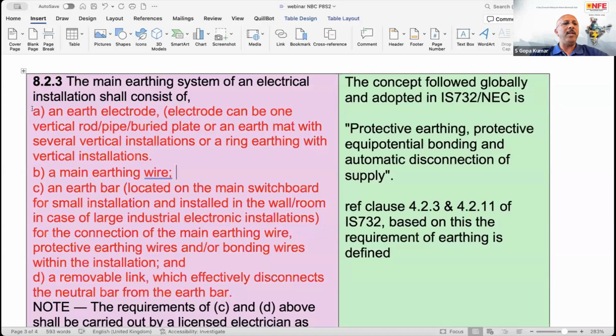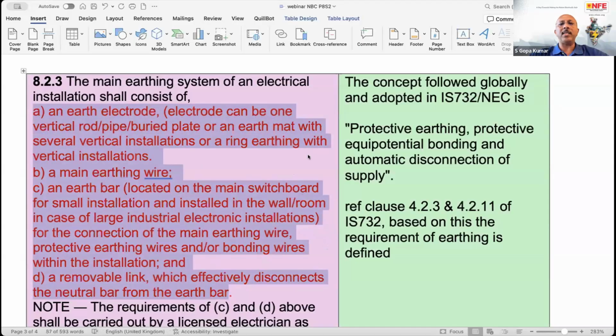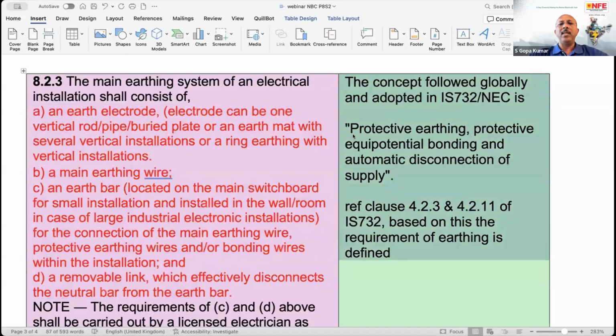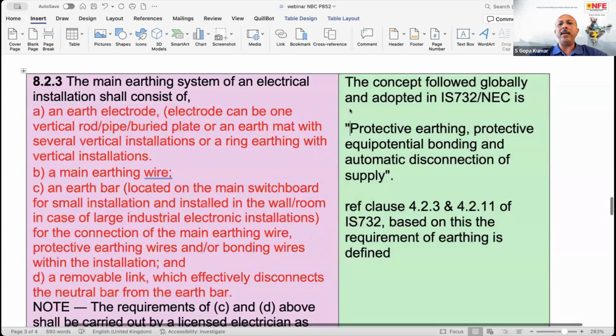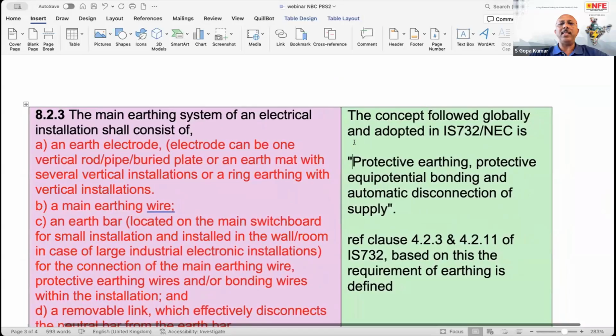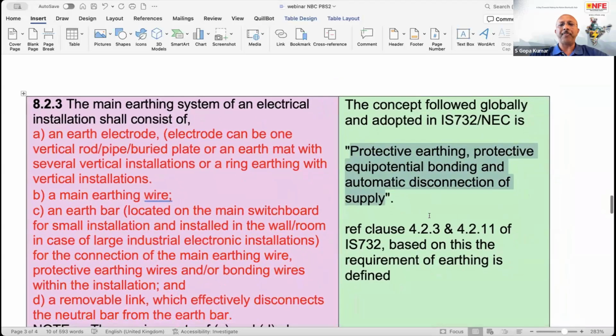Now you see, there is a new definition, as shown on the screen: earthing means the earth electrode and the connection to the earth electrode, and so on. Whereas the concept followed globally, also followed in IS 732 and NEC, is protective earthing, protective equipotential bonding, and automatic disconnection of supply.